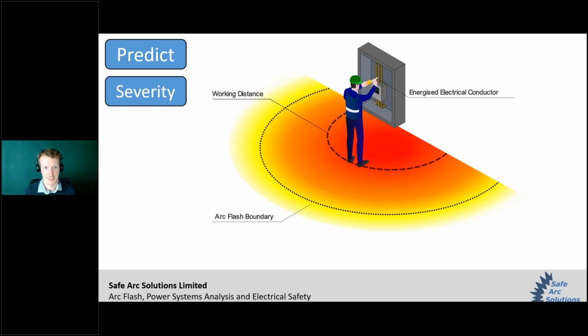The arc flash boundary is the second piece of important information that you get out of a study, and that expresses the distance at which you can imagine the arc is happening in the panel here at the energized electrical conductor. The arc happens and the energy dissipates out and spreads out and drops off as you get further away from where the arc happened. And as it drops to a point which is considered acceptably low, this is the arc flash boundary. It's got a value of 1.2 calories per centimeter squared, which is about the equivalent of holding your skin up to a burning candle. You don't want to hold it there for very long, but it's going to be an injury that you can recover from.